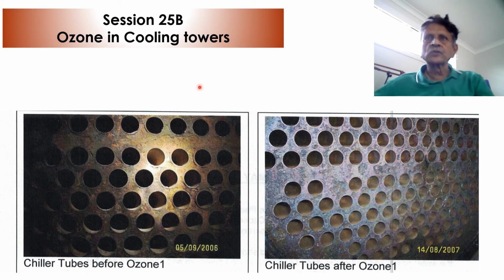This picture shows an ozone treated tower. A picture was taken before the installation, after it has been completely cleaned up, and 1 year later the chiller tubes were opened up, and this is what appeared.